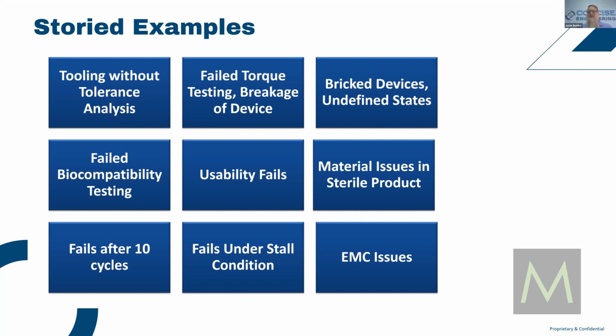Everybody have anything else? Justin, could you explain that thing with the Tyvek merging with another material real quick? Yeah, typically it's a shelf life study or a real-time aging study. The product itself, depending on how you package it, could be in contact with the seal layer. Over time you get a cold flow of those materials and they will merge. And when they merge, you cannot claim that the sterile barrier still exists, because you would basically peel it off and there could be holes there, right? And so you can't use that product.